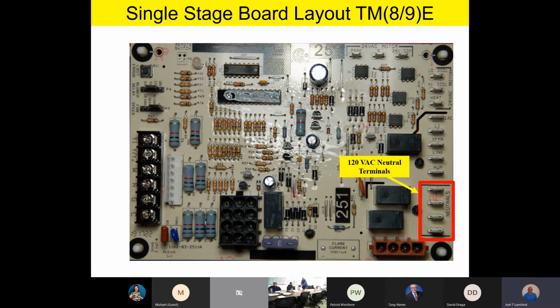There we go. Right below the HUM terminal, we have neutral terminals. Those neutral terminals are where all of our white wires, or the neutral wires coming in from our 120 volt components, will be tied in. We'll have a neutral wire, for instance, going up to the ECM motor. We'll also have a neutral wire going up to the transformer. And so that's where those will tie in.